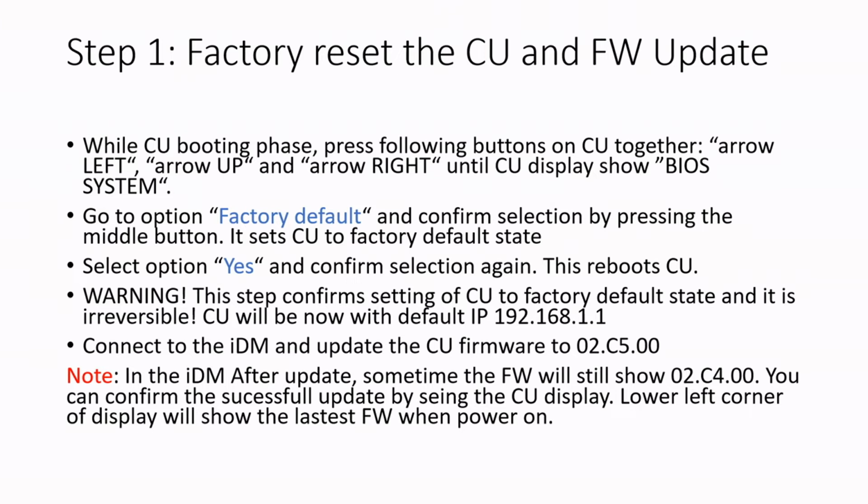Here are the steps you need to do before doing the cloud connection in the central unit. So when the CU boots up, press the 3 buttons, left, up and right arrow, until the display shows BIOS system. So go to factory default and press yes. So the steps confirm the setting of CU to factory default state.